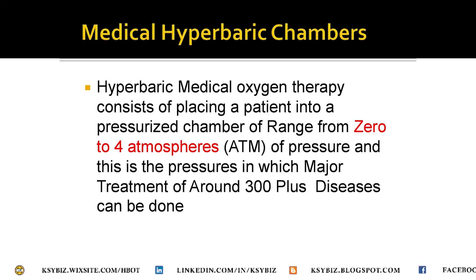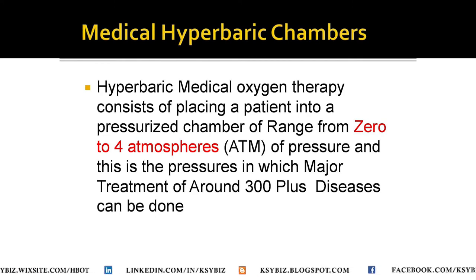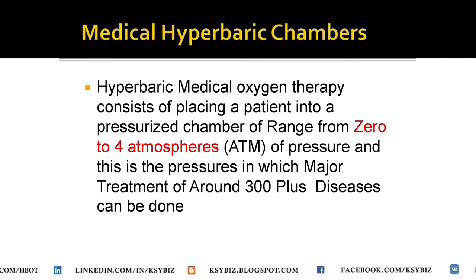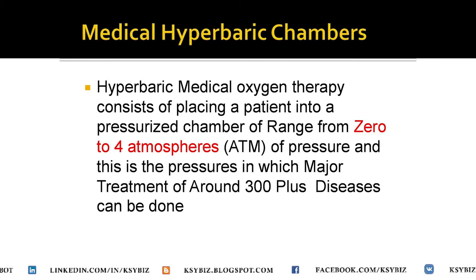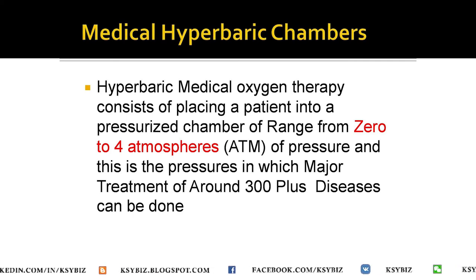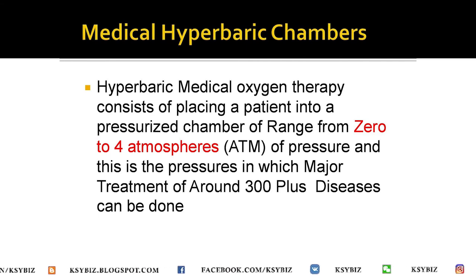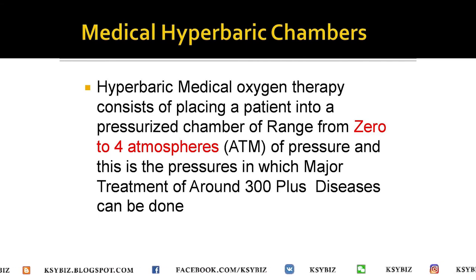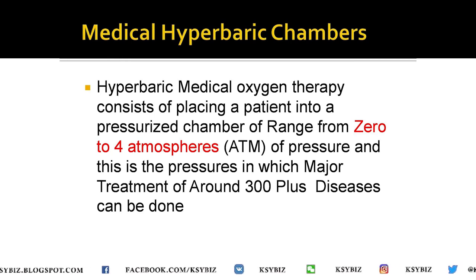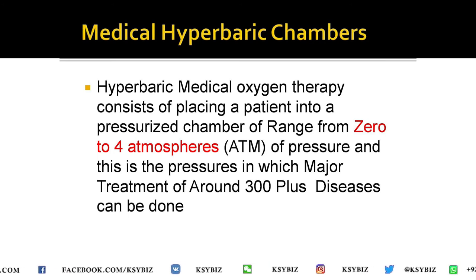This is what differentiates the medical hyperbaric chamber from the diving hyperbaric chamber. In medical hyperbaric chambers, the pressures range from zero to three atmospheres, and sometimes the full range is zero to four atmospheres, with the majority of treatments done under three atmospheres.